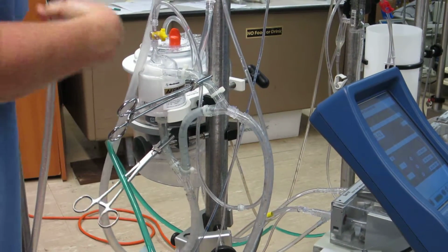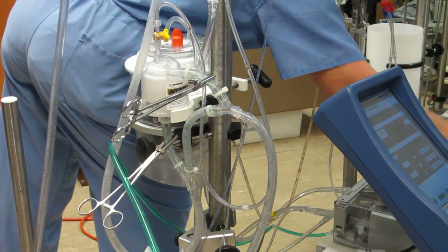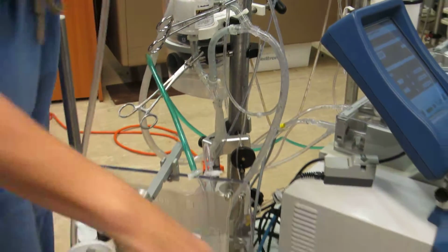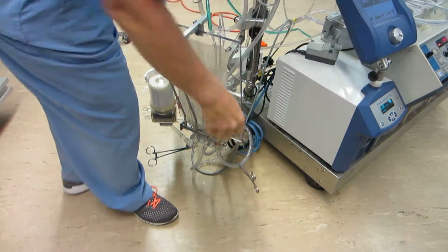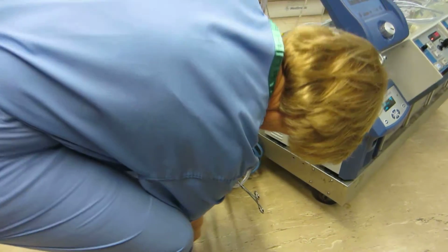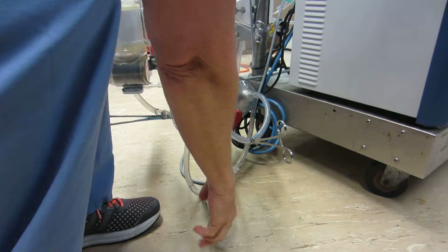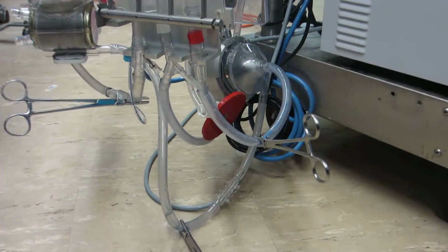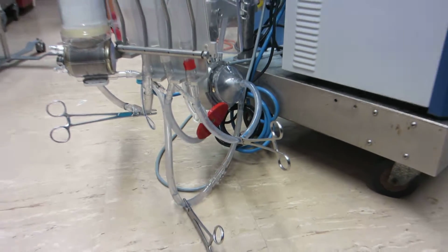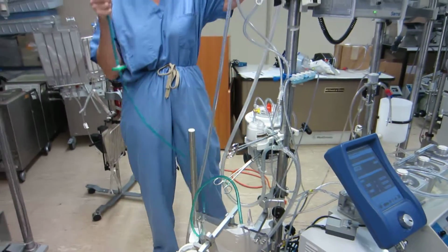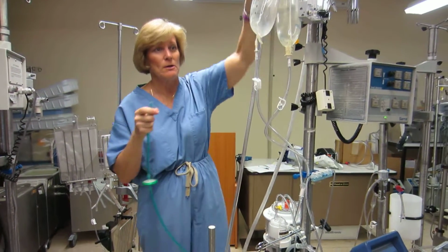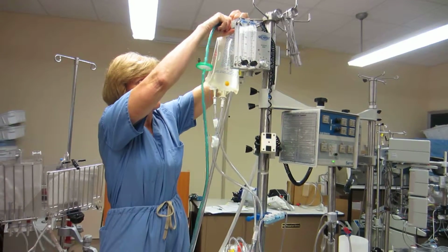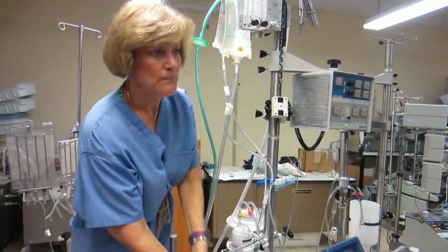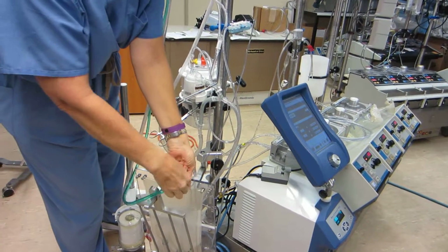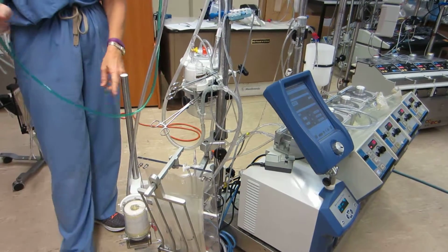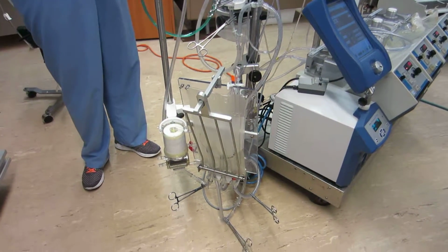How do we occlude a pump head? So we're working on a tether today, so I'm going to go ahead and put one on the inflow. And then I'm going to put one on the outflow distal to my flow probe, right? Mm-hmm. And then what do I have left to do? Change the ones. Gas off, stopcock off, isolate the filter, occlude my pump head, and then tank, right? Right? Mm-hmm. Did I forget anything? No leaks. Right? No leaks.